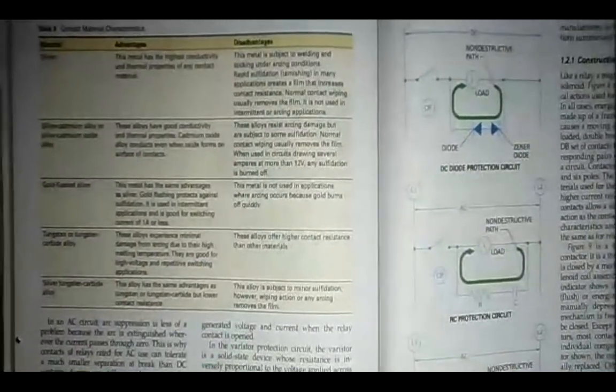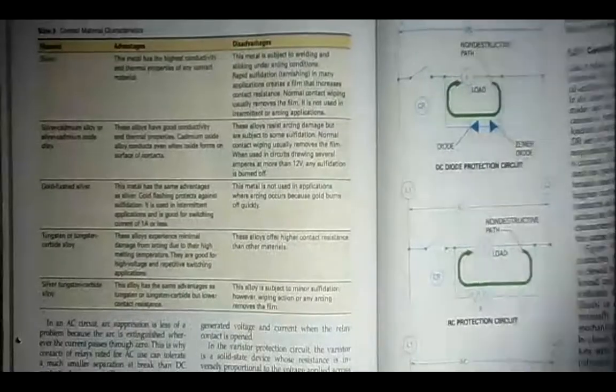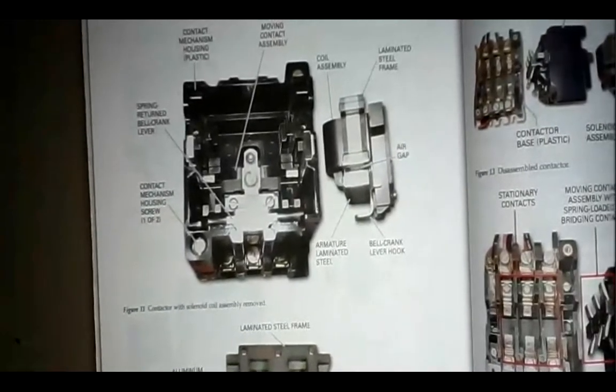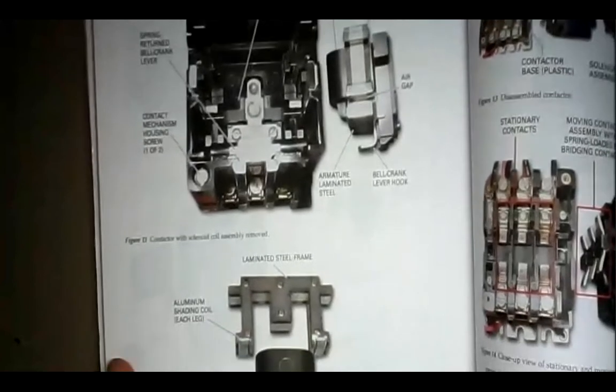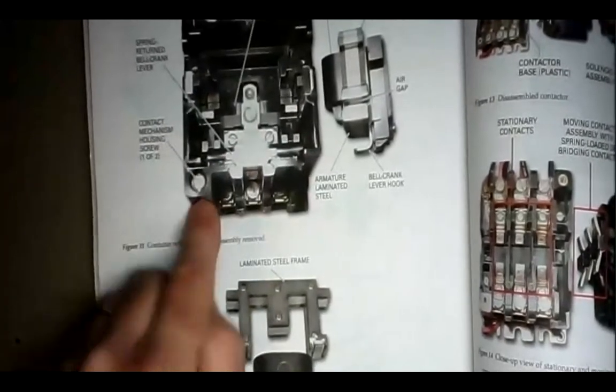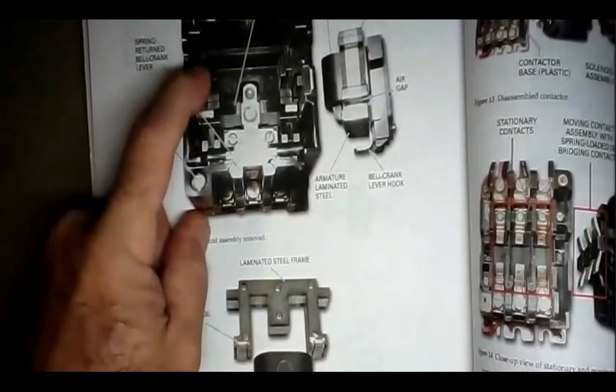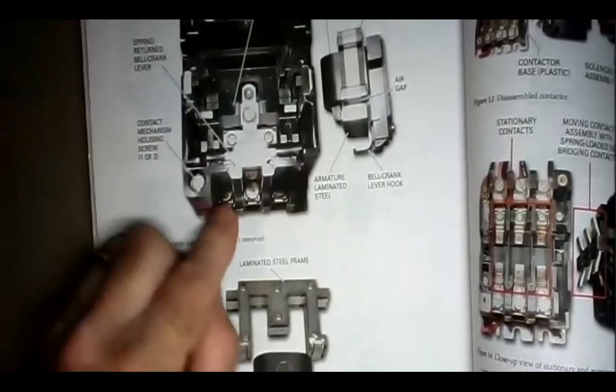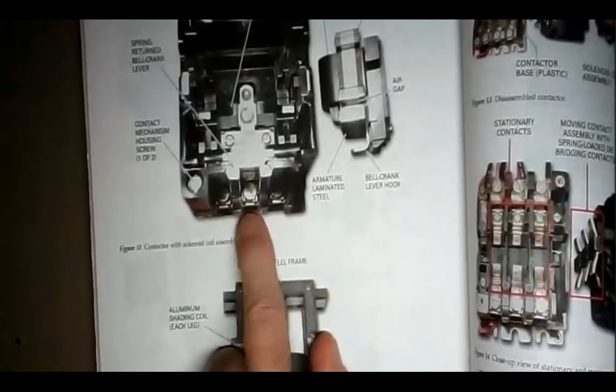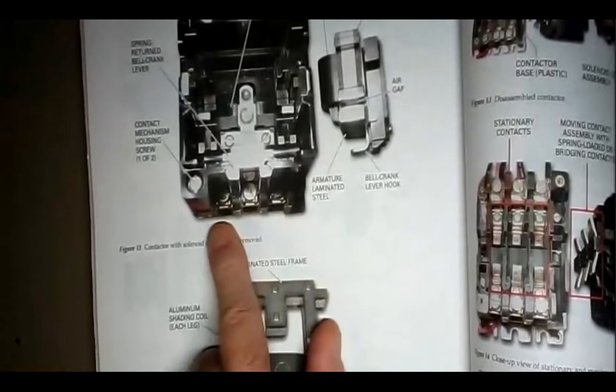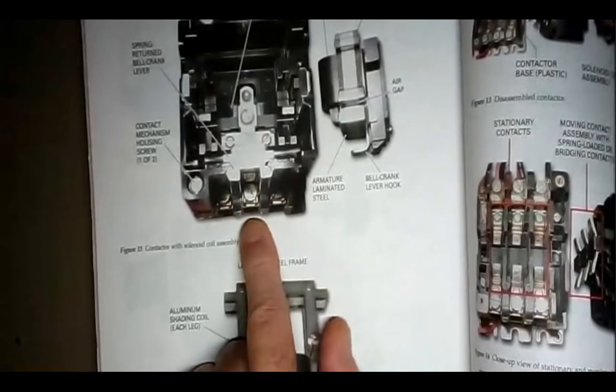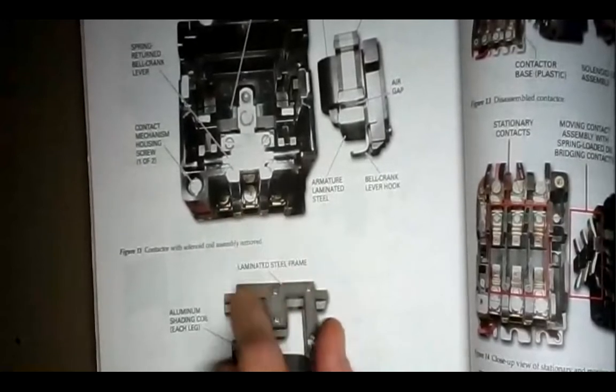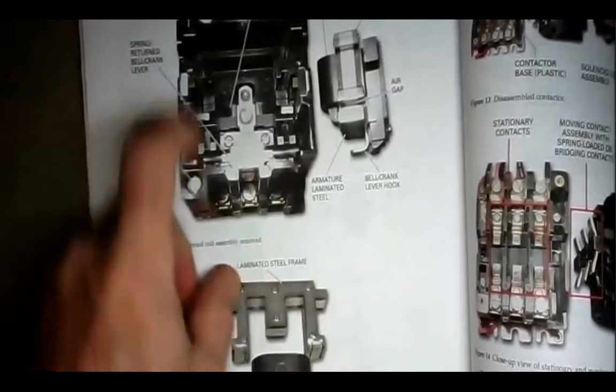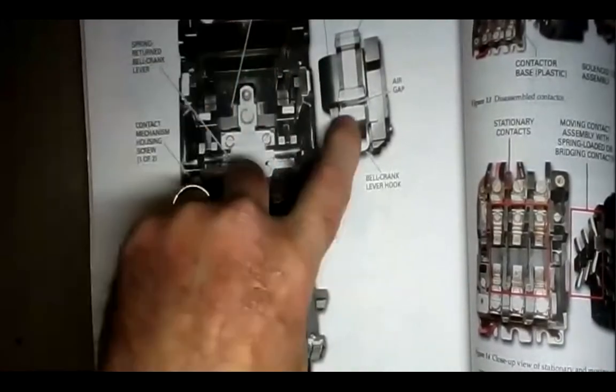I actually have no highlights on pages 8 or 9. Continuation of the discussion. Here's a nice exploded view of a motor controller. Here's the shell, and the contacts are inside here. We can't see them. Here's the exit points for the three phase, A, B, and C, or line 1, or T1, T2, T3. These are the T leads going to the motor. Line 1, line 2, and line 3 would be up here.